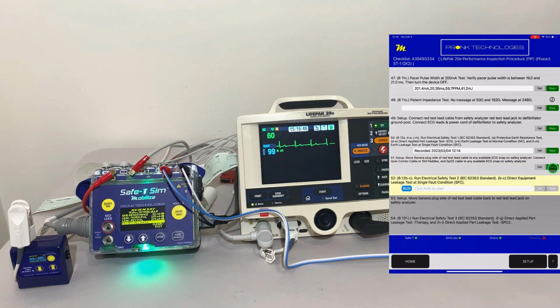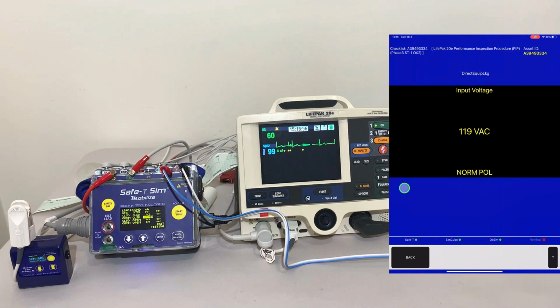And now we're going to run the second electrical safety test according to IEC 62353 standards, which is the direct equipment leakage test. So we'll go ahead and run that. And again, the procedure in the Mobilize app knows exactly what tests need to be performed. You'll see it here at the top again. Go ahead and do that leakage measurement, with the device configured to perform the direct equipment leakage test.